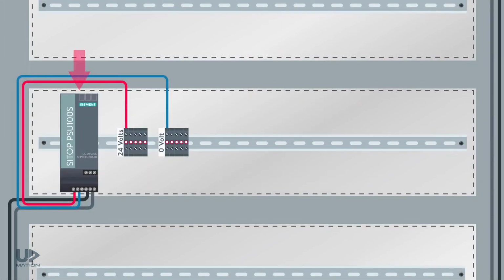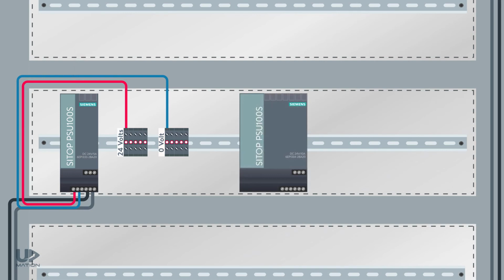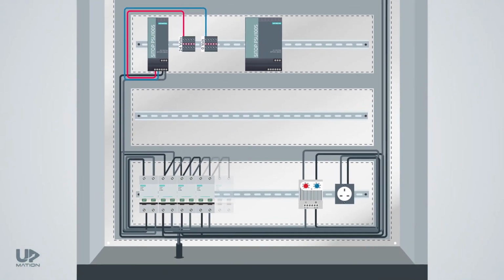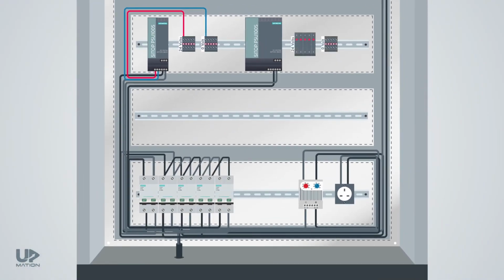I have planned to dedicate this power supply to the PLC CPU and its input-output modules to even protect them more against any faults that may happen outside of the control panel. Therefore, I should consider a separate power supply with sufficient amperage for feeding the devices at site, such as instrumentation devices. I repeat the same procedure for this power supply, but this time, instead of ordinary terminal blocks, I consider some fused terminal blocks to protect the power supply against drawing extra amps by the devices at site. I'll explain that with a practical example in a video about troubleshooting the control panels.